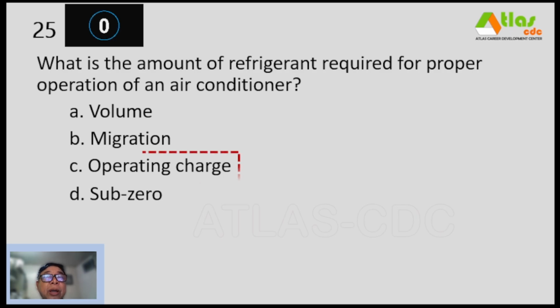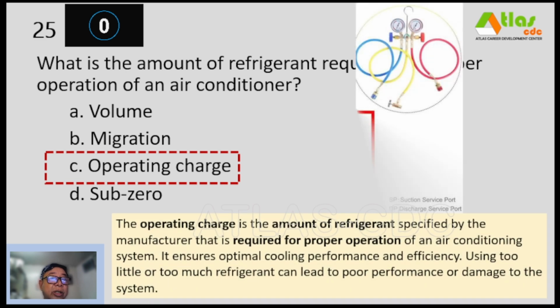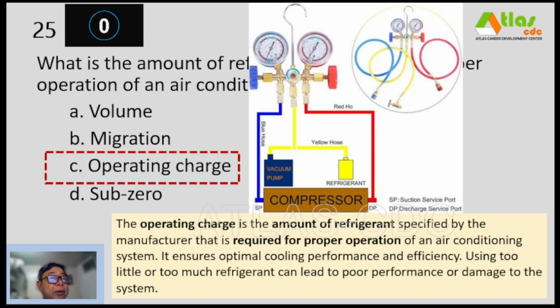And our correct answer is letter C, operating charge. So the operating charge is the amount of refrigerant specified by the manufacturer that is required for proper operation of an air conditioning system. It ensures optimal cooling performance and efficiency. Using too little or too much refrigerant can lead to poor performance or damage to the system.